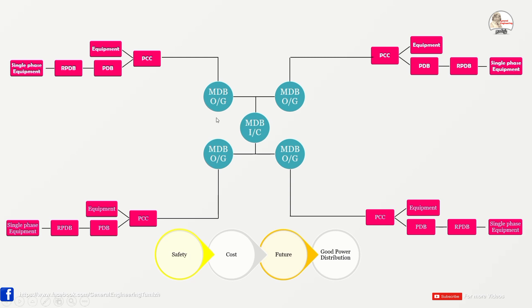The second consideration is cost. If the transformer and MDB are placed at one end of the plant, cable length for power distribution across the whole plant increases, which raises cable cost, cable tray cost, installation cost, and manpower cost. So it is better to place the MDB and transformer in the middle of the plant.